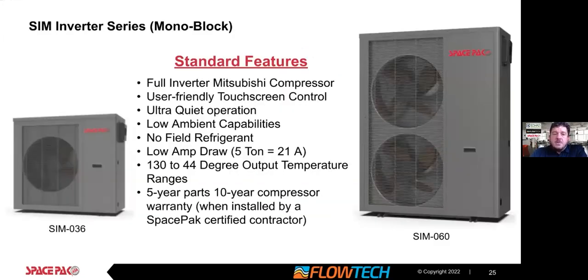So we'll get into the monoblocks, our daily driver, our workhorse. They've had phenomenal performance in about a year and a half, 2 years of seeing these out in the market. We were lucky enough to help roll them out in our market. There's the 3-ton on the left, the 5-ton on the right. That's an inverter compressor that allows the units to modulate, ramping down their output to match loads. It's got a touchscreen control. Quiet operation is a big one out here in many areas. We get that question a lot.